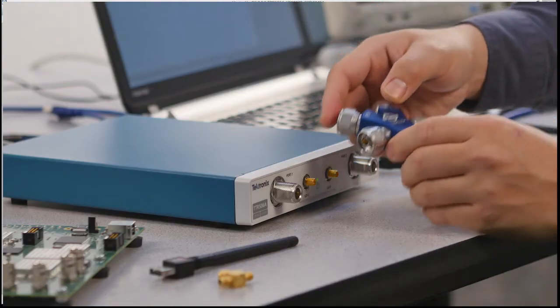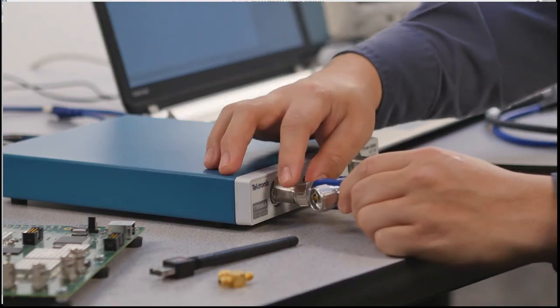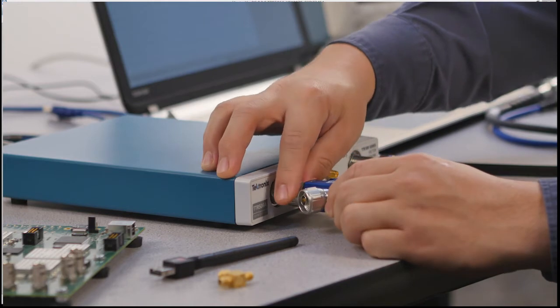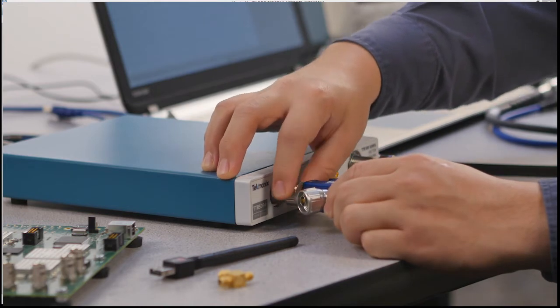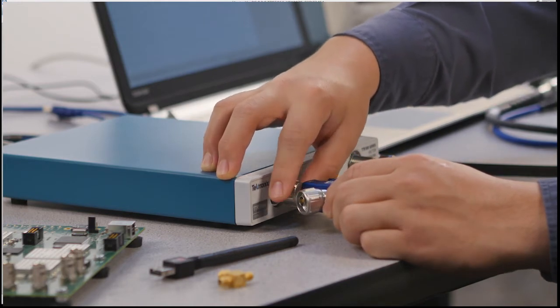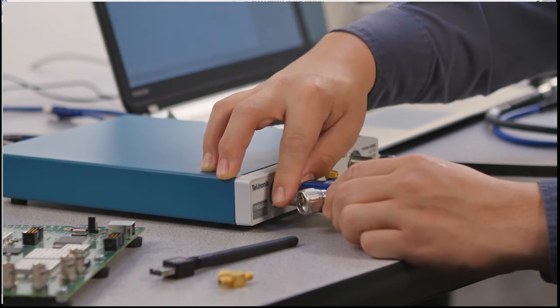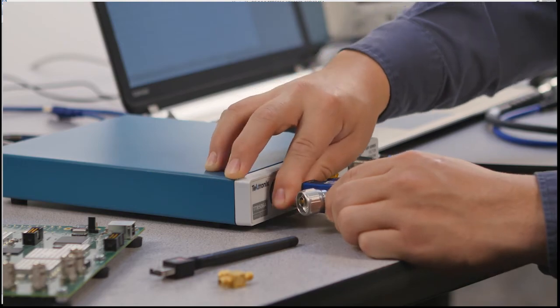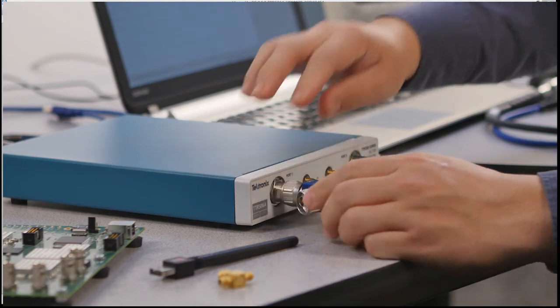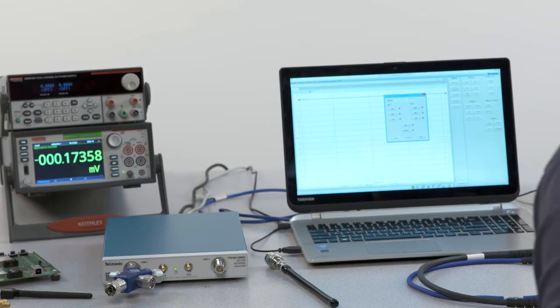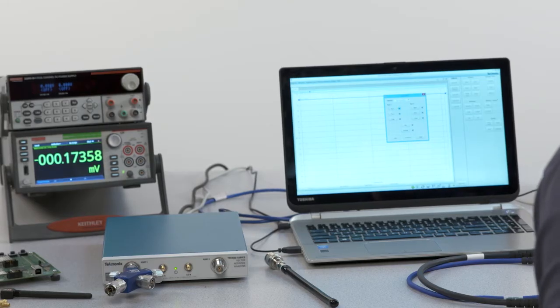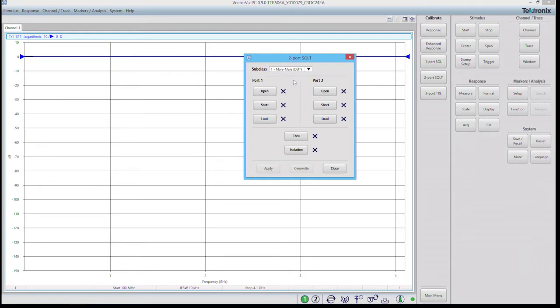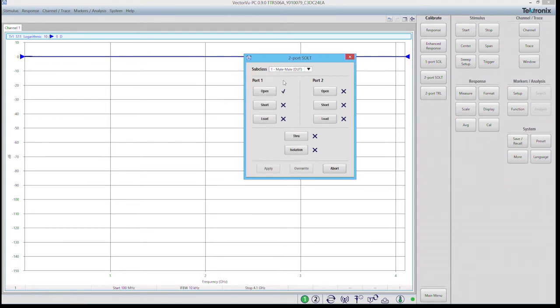Now to do so I'm going to take my four-in-one mechanical cal kit and take the open port and connect it to port 1. Once I've made a secure connection I'm going to click the open button and it will register that measurement.